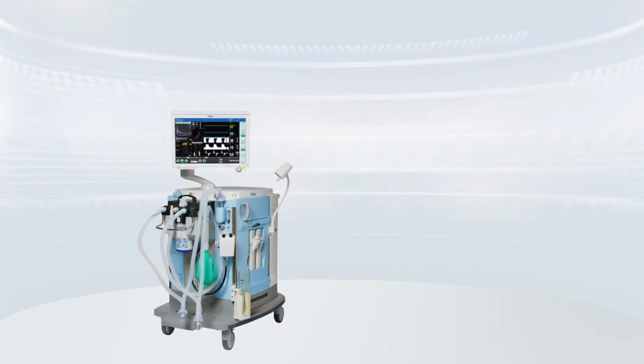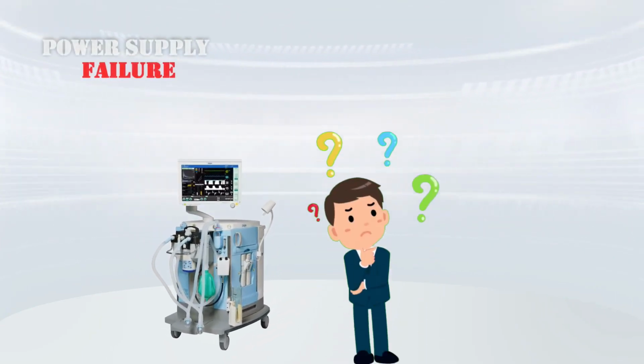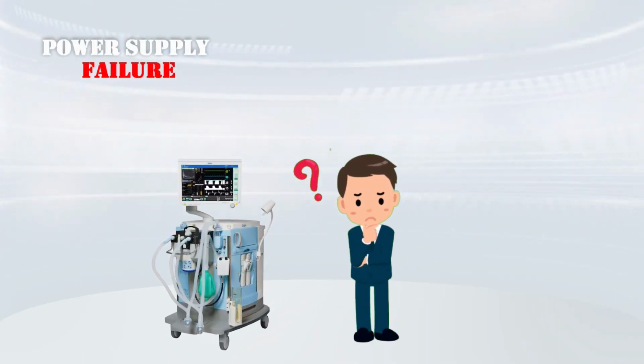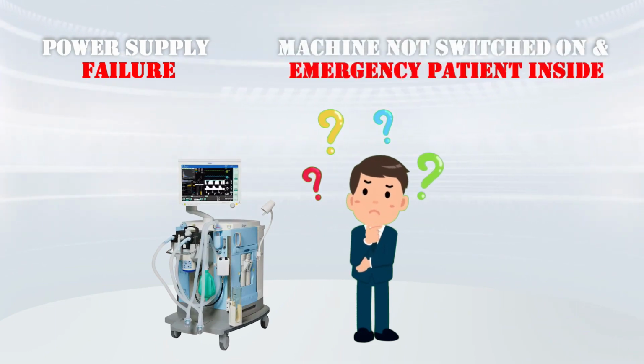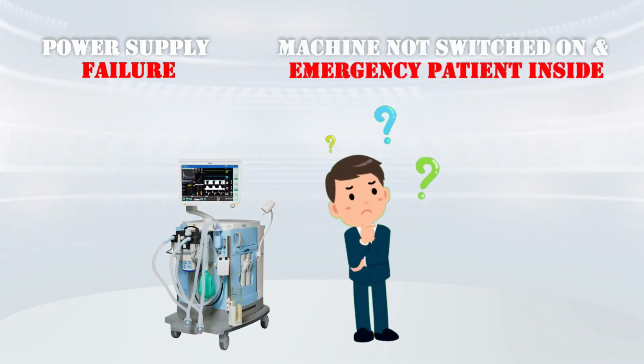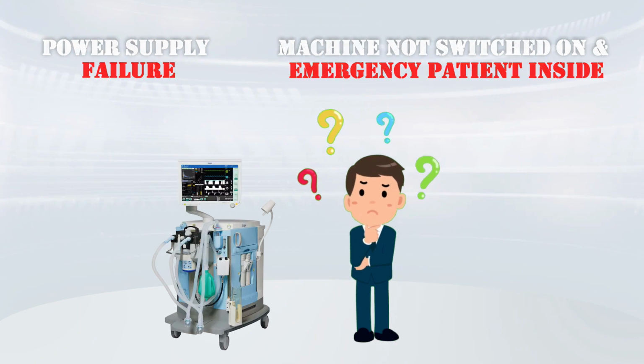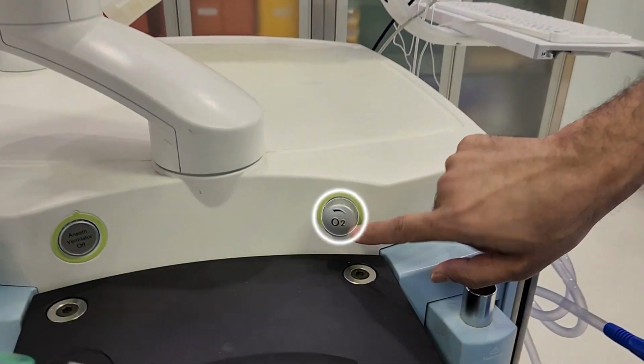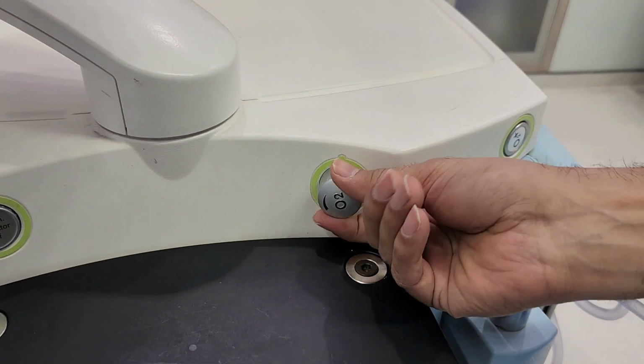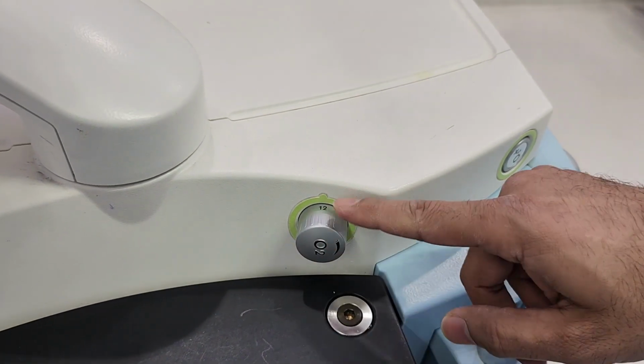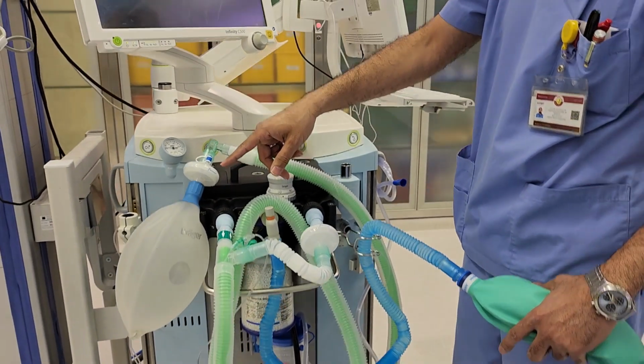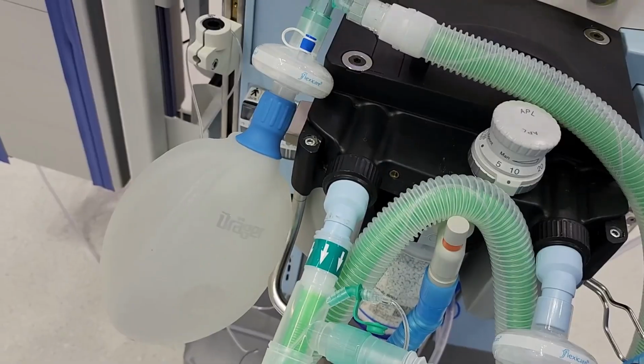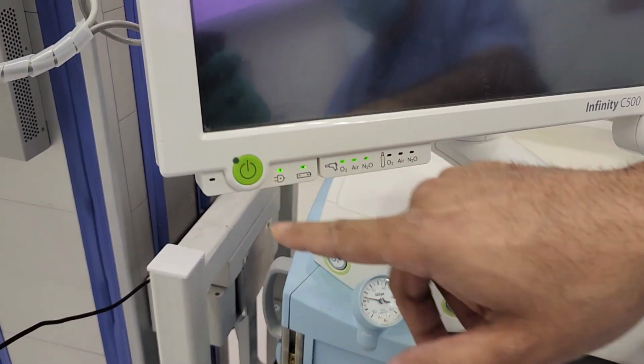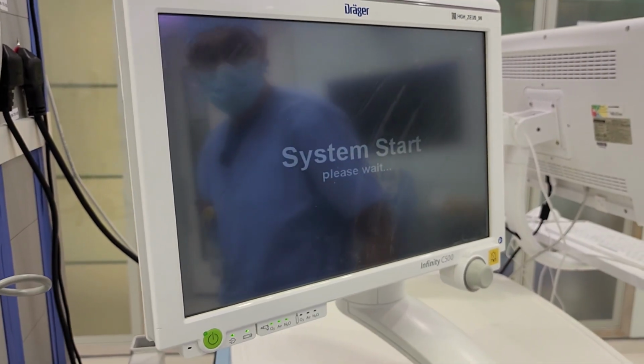Now, what if the gas supply is okay, but there is a complete power supply failure? Or in case we get an emergency patient, and the machine was not switched on? We can still ventilate the patient by activating the emergency oxygen delivery system. We will be able to ventilate the patient, just as we do with the ambu bag. And remember, this works even if the machine is switched off, or even in case of complete machine failure.